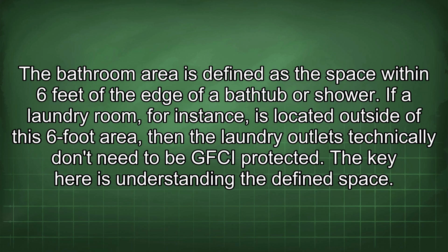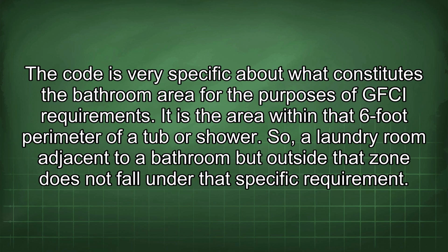If a laundry room, for instance, is located outside of the 6-foot area, then the laundry outlets technically don't need to be GFCI protected. The key here is understanding the defined space. The code is very specific about what constitutes the bathroom area for the purposes of GFCI requirements. It is the area within that 6-foot perimeter of a tub or shower. So, a laundry room adjacent to a bathroom but outside that zone does not fall under the specific requirement.